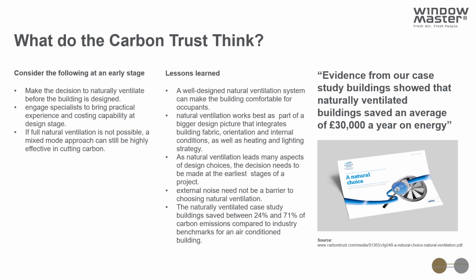You don't just have to take our word for it. The Carbon Trust did a really interesting study a few years ago, which is available online now, and they found that the energy consumption of those buildings which were effectively designed and delivered using natural ventilation demonstrated energy savings between 24 and 71% compared to other buildings of a similar type. They also demonstrated that those with effective natural ventilation solutions saved on average £30,000 a year on energy.